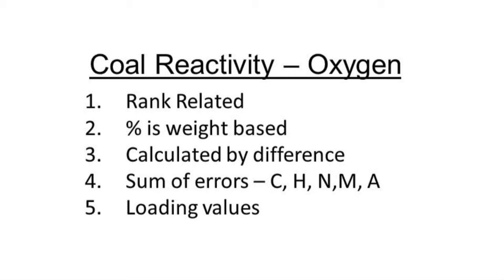Just like volatile matter, the oxygen value goes up as the calorific value goes down. One way to take a closer look at the oxygen impact on a coal is to look at the moisture-ash-free (MAF) calorific value. Bituminous coals have high MAF BTUs per pound or kilocalories per kilogram because there's very little oxygen. When we look at MAF values, we see that as the oxygen concentration goes up, the calorific value goes down — so just looking at the part that burns on a MAF or DAF basis, lower BTUs are probably being caused by higher oxygen concentrations.